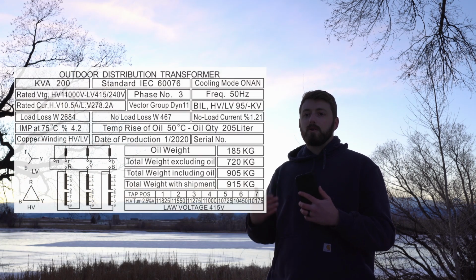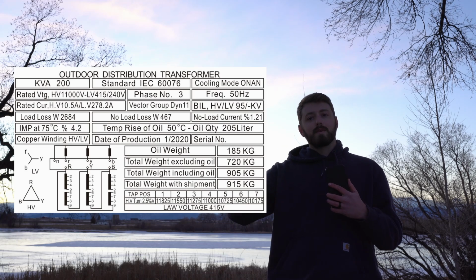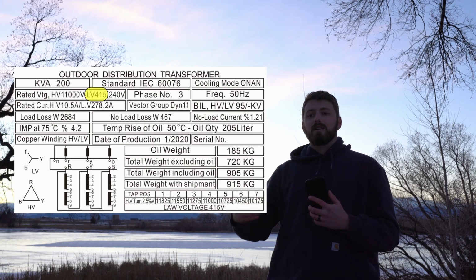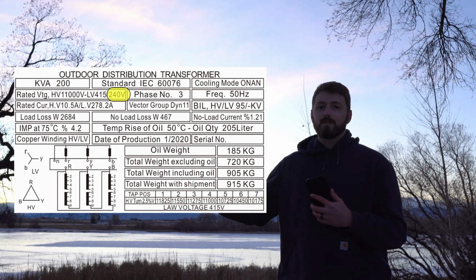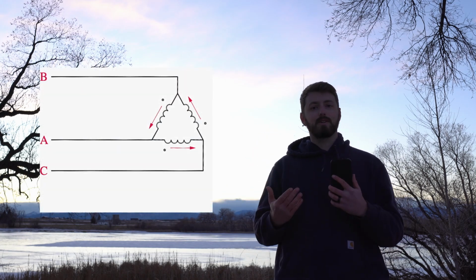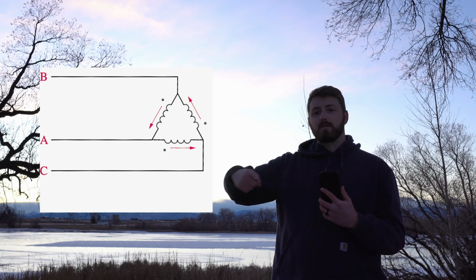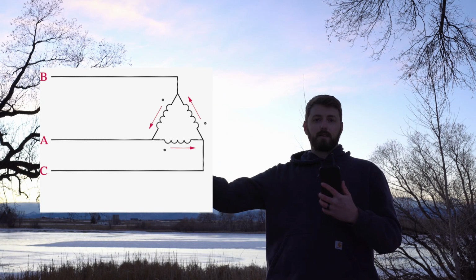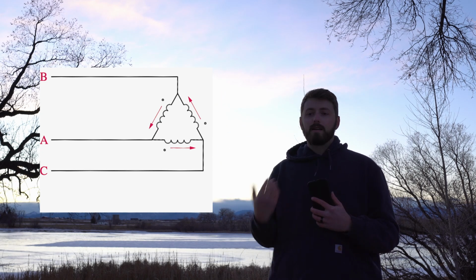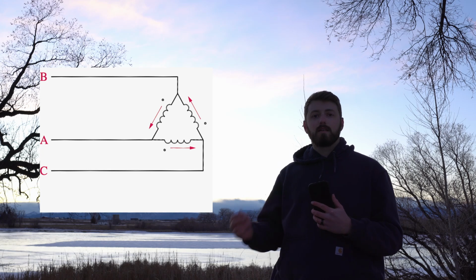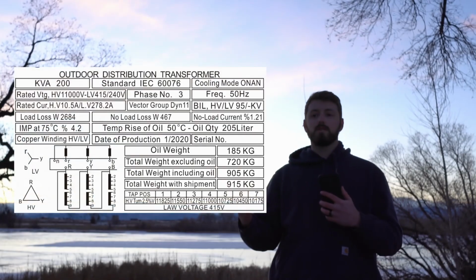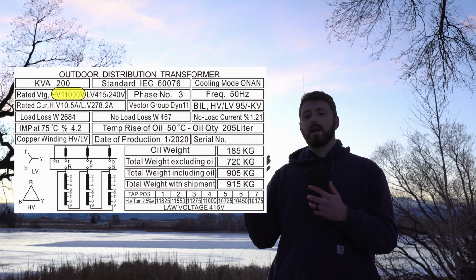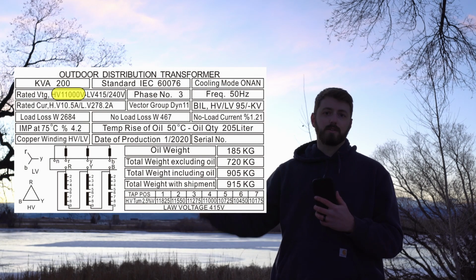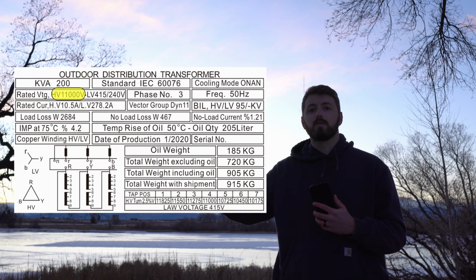Anytime you see a transformer or a motor nameplate that has 2 numbers with a slash between them, the bigger number is the phase to phase and the smaller one is the phase to neutral voltage. Some 3-phase systems are connected in what we call a delta configuration because the phasor diagram looks like a triangle or the Greek letter delta. It's really creative. On a delta system, we can only have loads that are connected between 2 or 3 of the hot lines. The voltage for a delta system will only have one number, and it's the phase-to-phase voltage. So it's the phase between A and B, B and C, or C and A.